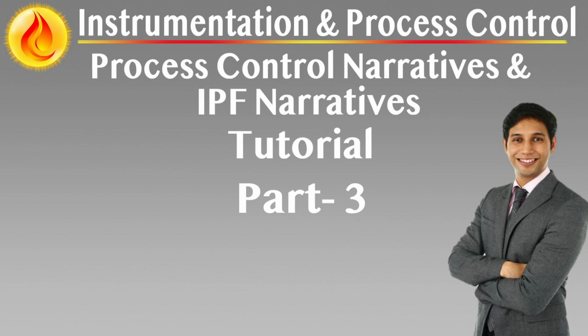Most likely required operator action specifies the typical expected operator response in most situations, i.e. 80% of the time. This helps operators respond confidently and quickly when the alarm is activated and supports alarm training and procedural alignment. Less likely required operator action describes any secondary or alternate actions that may occasionally be required depending on operating conditions, i.e. 20% of the time. This anticipates variation in process behavior or upstream-downstream conditions.